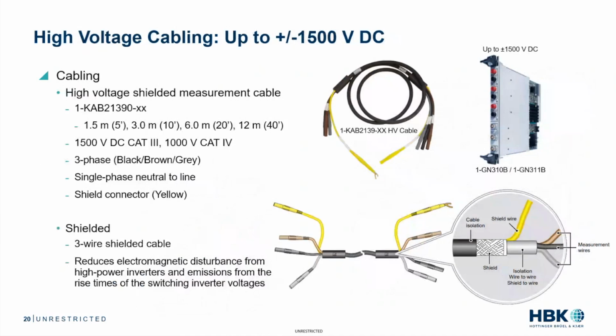Let's talk a little bit about high voltage. So basically, ideally, you want to use shielded cable there as well, but the cable has to be able to withstand high voltages. You want to have 1500 volt DC Cat 3 cable in most cases, especially with the higher voltages that are forthcoming in the industry.